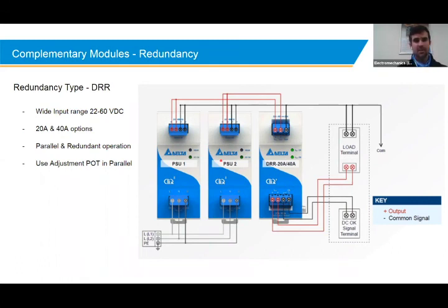In redundant operation, if you've just got the second power supply there for a backup, then obviously balancing the voltages out to 5% or whatever is not that necessary. One power supply will do the work. If it fails, then the other power supply would automatically take over anyway. So that's the DRR redundancy module, 20 and 40 amp options.